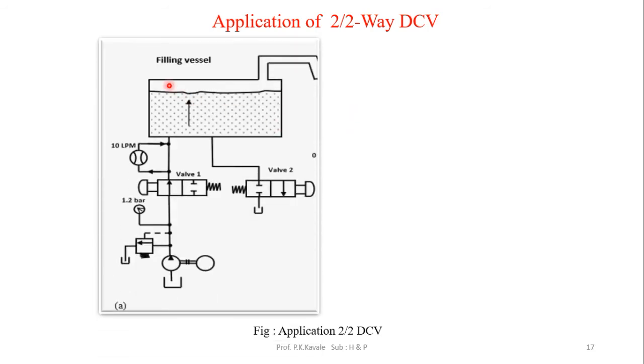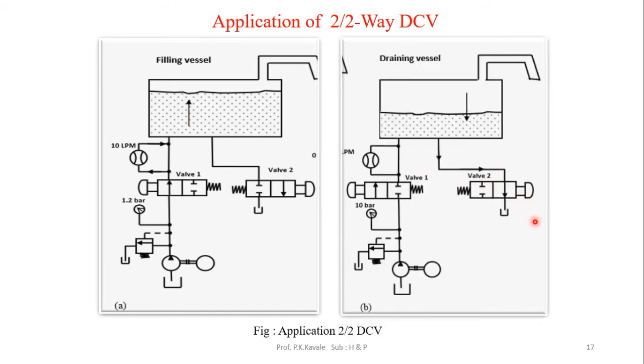Application of a 2/2 DCV: consider a tank that needs to be filled. A pump and pressure relief valve are connected. The first 2/2 valve is normally open, so flow is diverted toward the tank, filling it. A second valve is used to drain the vessel — it is normally closed, and when pushed, liquid moves out for draining.